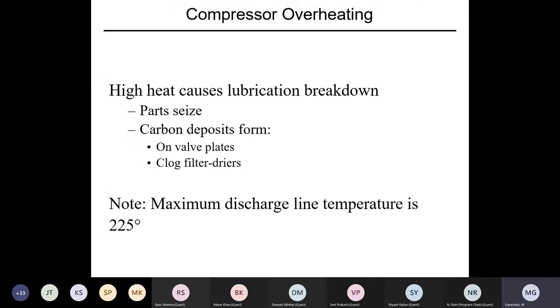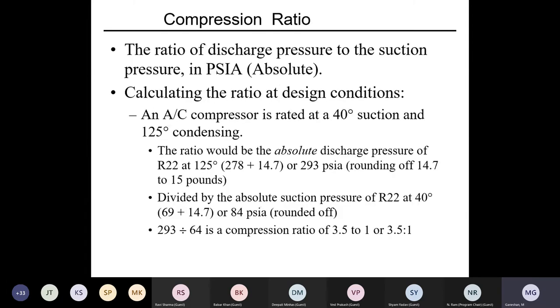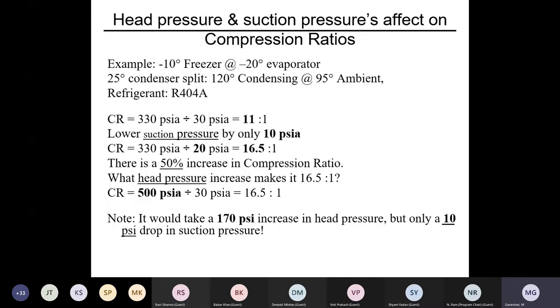We have seen that in any compressor, if the maximum discharge line temperature goes beyond 225, decomposition of the refrigerant begins, which is the next level. So we should not allow it to go that far. Now, the normal compression ratio will go up, but the moment the suction goes a little lower, the compression ratio will be higher. For an air cooled compressor the ratio is normally around 3.5 to 4.5, but if that ratio has become 6, then naturally you are asking the compressor to work much harder.